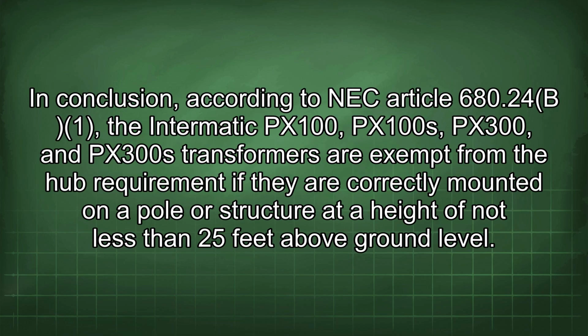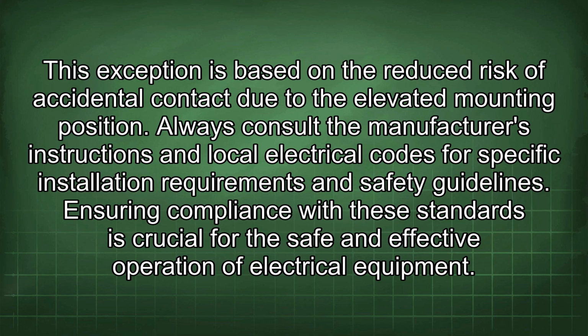In conclusion, according to NEC Article 680.24(B)(1), the Intermatic PX100, PX100s, PX300, and PX300s transformers are exempt from the hub requirement if they are correctly mounted on a pole or structure at a height of not less than 25 feet above ground level. This exception is based on the reduced risk of accidental contact due to the elevated mounting position. Always consult the manufacturer's instructions and local electrical codes for specific installation requirements and safety guidelines. Ensuring compliance with these standards is crucial for the safe and effective operation of electrical equipment.